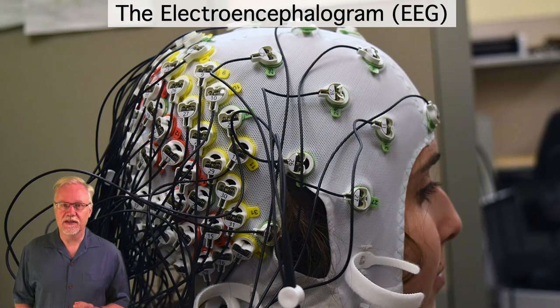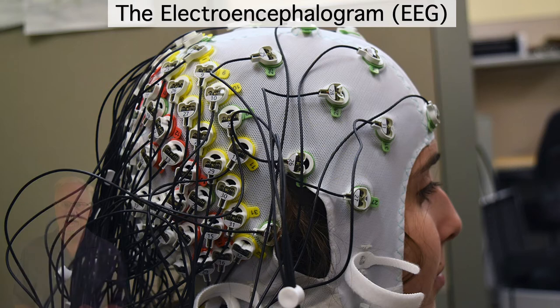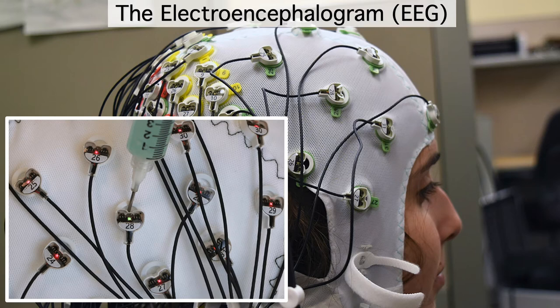To record the EEG, we put a set of electrodes on the subject's head. In most labs, the electrodes are embedded in a cap. The electrodes don't directly contact the skin. Instead, we squirt in a conductive gel that makes contact between the skin and the metal electrode pellet.